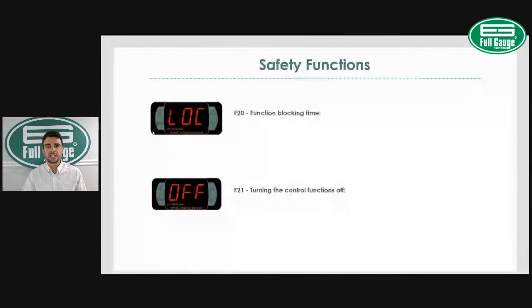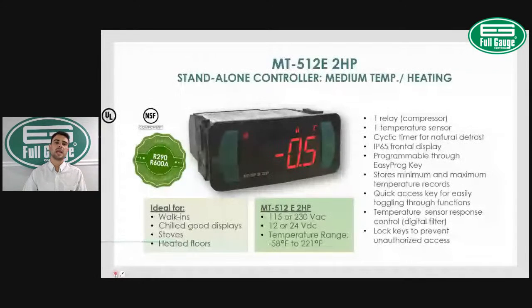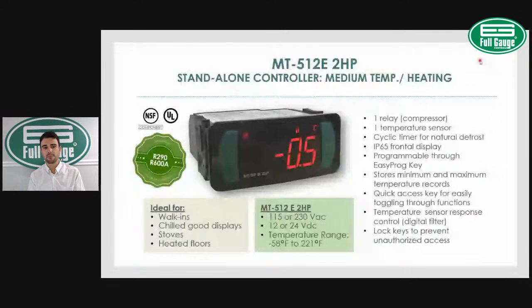So again, let's revisit this controller, MT-512E. Good for medium and high temp applications. It's a dual voltage controller, 110 or 230. Has got 2 horsepower relay output, 1 temperature sensor, built-in timer for off-cycle defrost, IP65, which is water protection. The display is waterproof. Programming can be through the EasyProg.